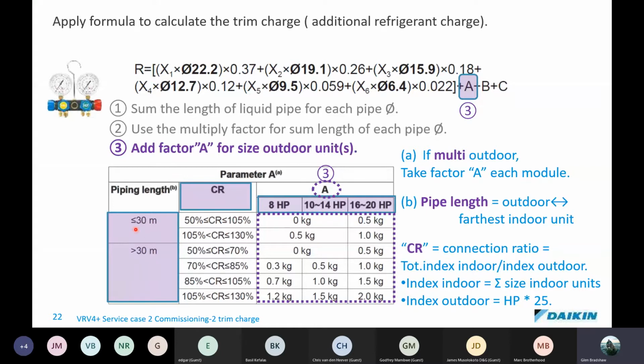Okay, first of all, if the total pipe length was less than 30 meters, then we see that some of the condensers would not need any additional amount added if they fell within these capacity ratio percentages. But for some of them, if they were to exceed these or fall into these categories, we would have to add this amount per condenser that fell within those horsepower ranges. All right, so the calculation gets a little bit more complex from there.